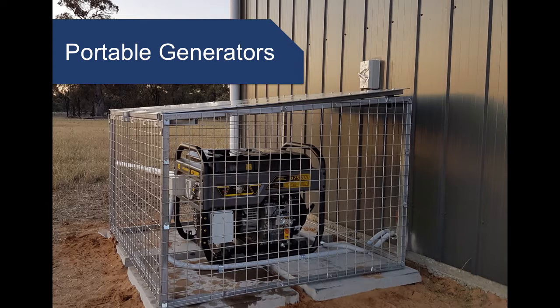Yeah, which is good. Aaron, I was just wondering what voltage is too high. I think 256 is around about where some of the settings are. I think they've got different voltage settings in the inverter for different periods. So if it goes up to 256 or something for a short period, it will click out. Or if it's sustained at 253 for a longer period, it might trigger the inverter to drop out.